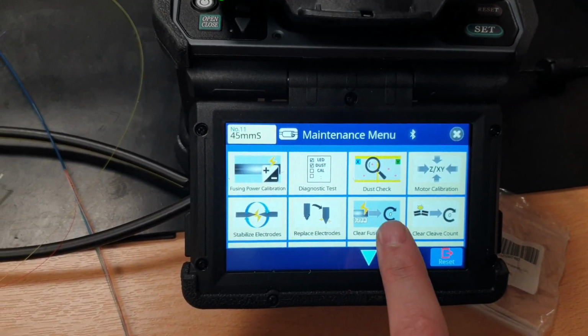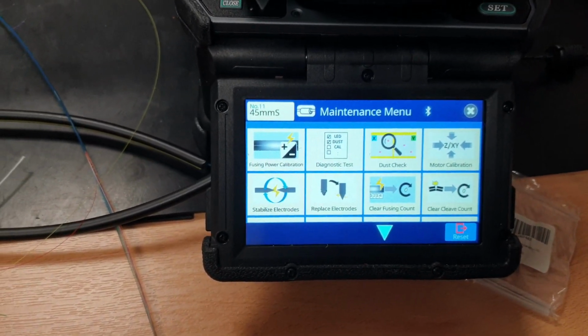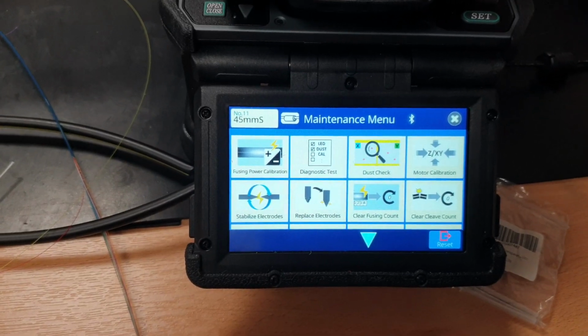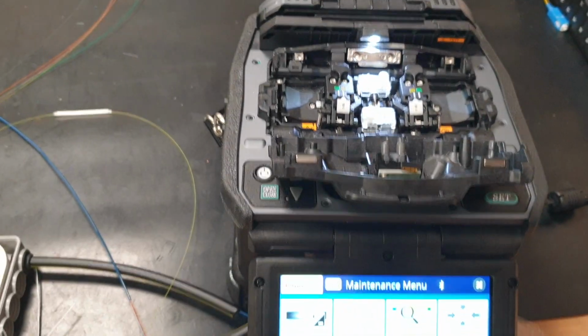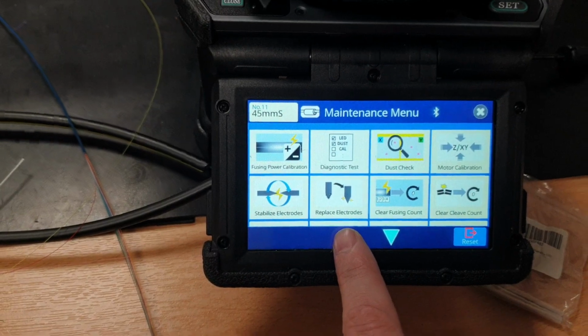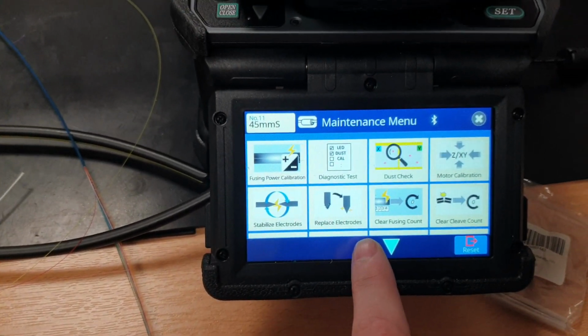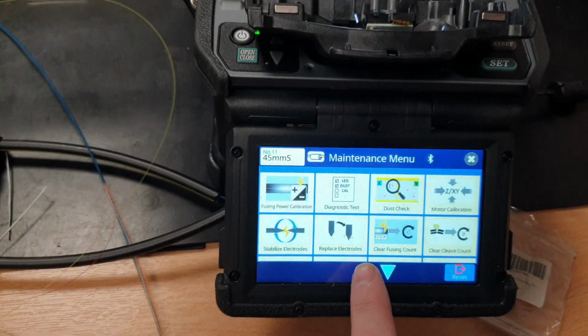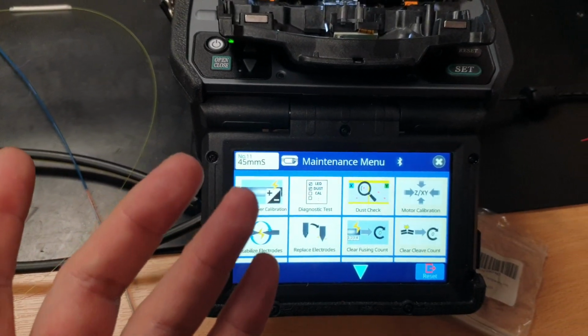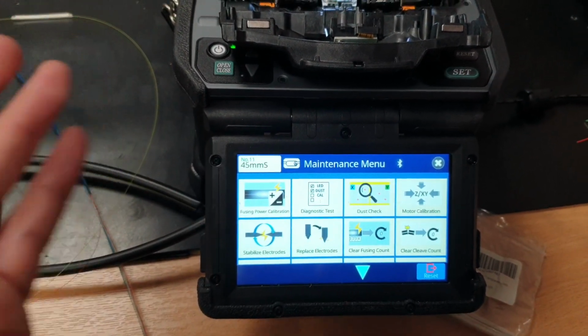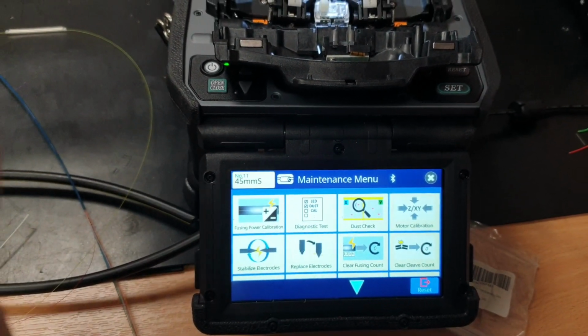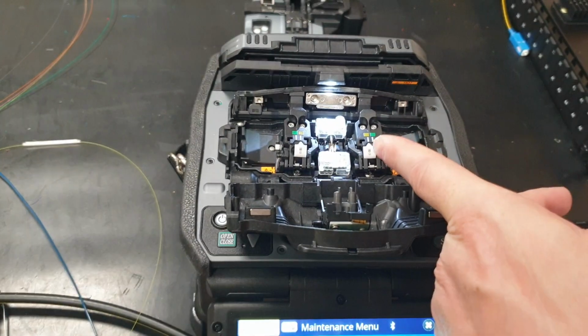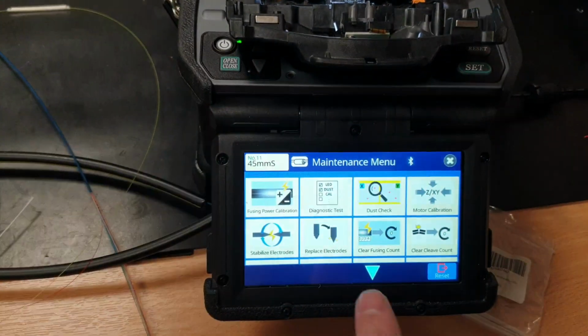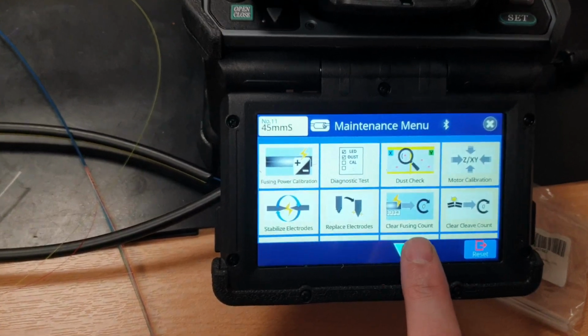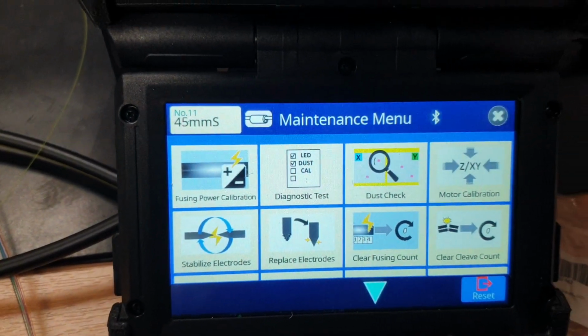Now the fusing count, the reason why it calculates how many times you've fused two fibres together, is in relation to actually replacing the electrodes. Now it should say in the manufacturer's guide, let's say it's a fictitious figure but using it as an example, your manufacturer's guide might say you can do 3,000 splices with those electrodes and then they need changing. That's a good way of having a check how many splices you've done before those electrodes need changing.